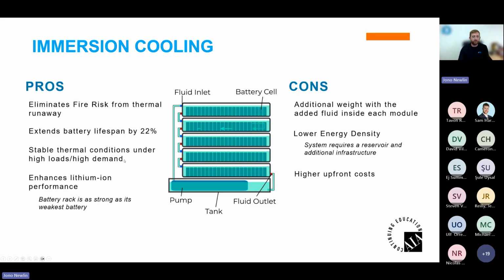It has stable thermal conditions under high loads and high demand, so this liquid stays in place. These esters that can be deployed in this space are typically used in transformers exposed to much higher heat. So this liquid is very stable during the high demand heat times of the batteries - it doesn't compare at all to where they've already been deployed in transformers.